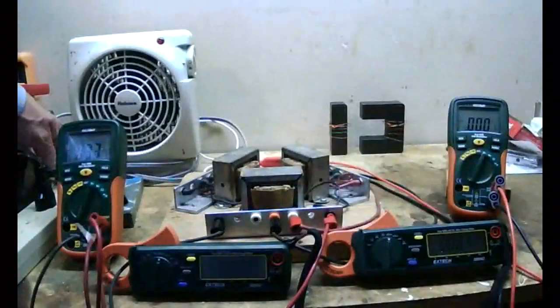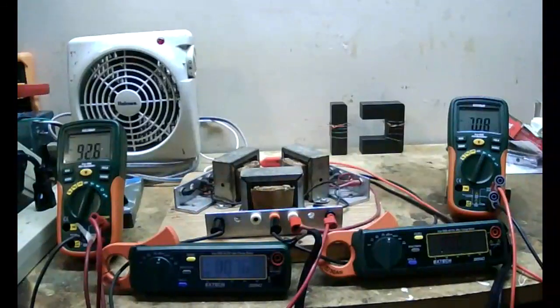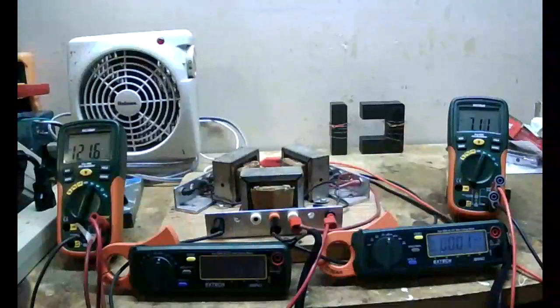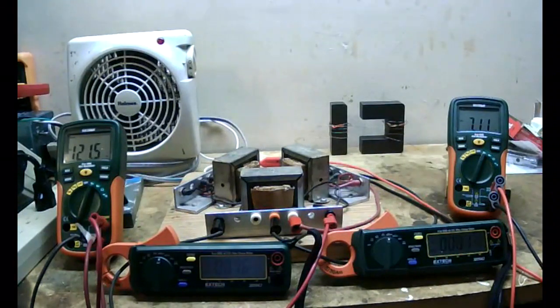I'm going to energize the whole thing through the outlet strip, and I'm going to take these readings. So what I have is open circuit. You'll be able to see all of these in a moment. At open circuit, primary voltage is 122. Secondary voltage is 7.1. So V1 magnitude, 122 volts, rounding off. V2 magnitude is 7.1 volts. Secondary current is reading very close to 0. It's reading actually 1 milliamp, and that is noise in that last digit.